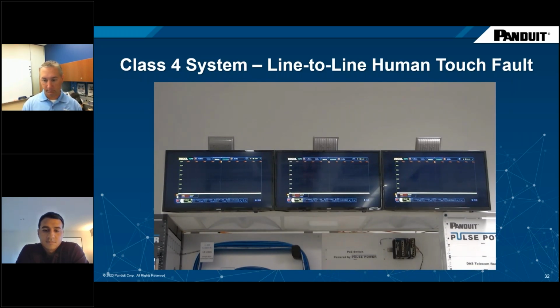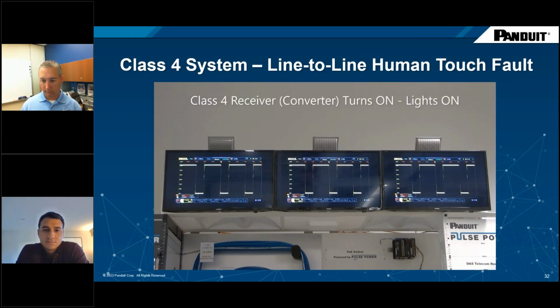The system knows that the fault is not there anymore, so it takes a few seconds before it turns back on. Now with pulse current being delivered again to the converter, the converter takes a few seconds before it can turn back on and provide power to the lights.